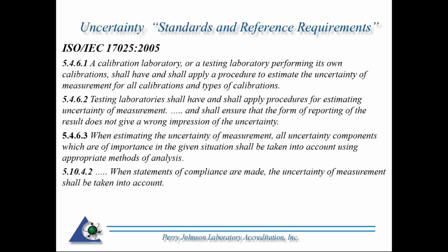5.4.6.2, and this is an abbreviated form of what's in the standard. Testing lab shall have and apply a procedure for estimating uncertainty of measurements and shall ensure that the form of reporting of the result does not give a wrong impression of the uncertainty. And we're going to look at this a little further as we capture it in PL3, which is our policy, PJLA's policy for measurement uncertainty.